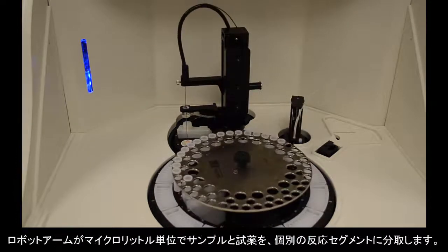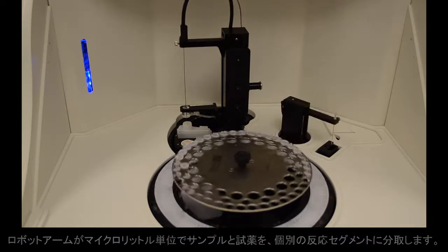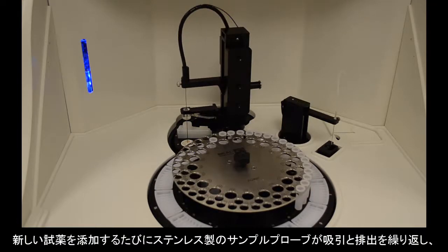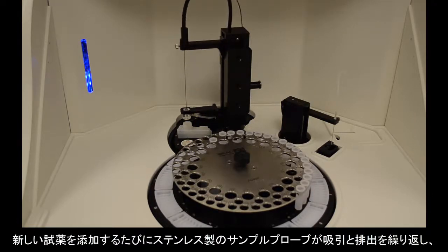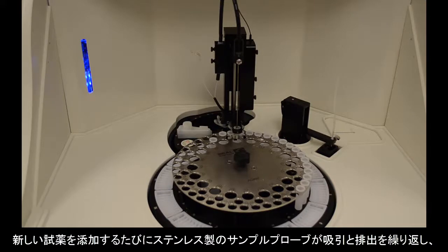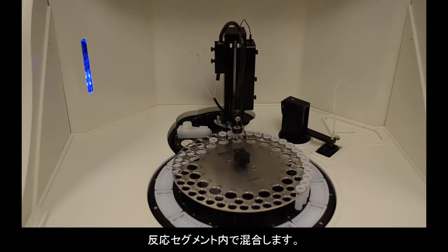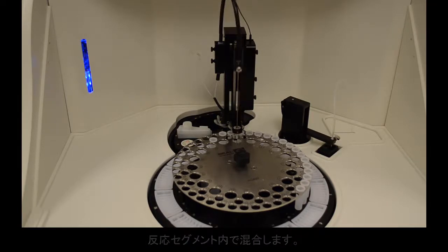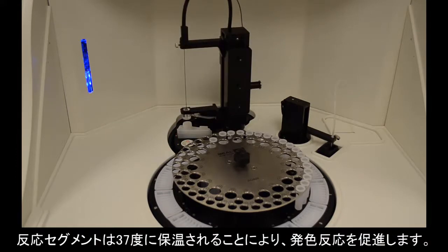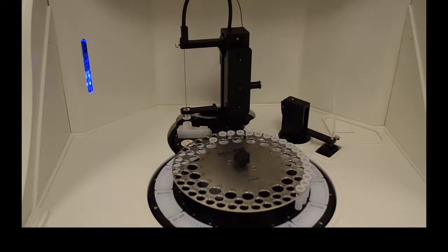The robotic arm picks up microvolumes of reagent and sample and dispenses the reaction liquid into a discrete reaction well. Each time a new reagent is added, the stainless steel sample probe mixes the reaction liquid by repeatedly aspirating and dispensing the reaction liquid into the reaction well. The reaction segments are incubated at 37 degrees Celsius to help catalyze the color reaction.